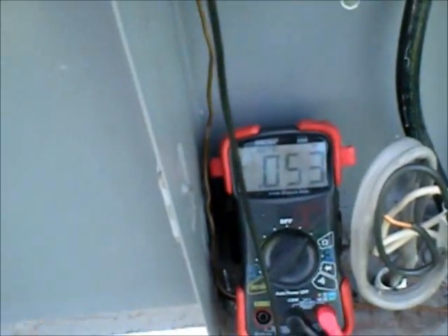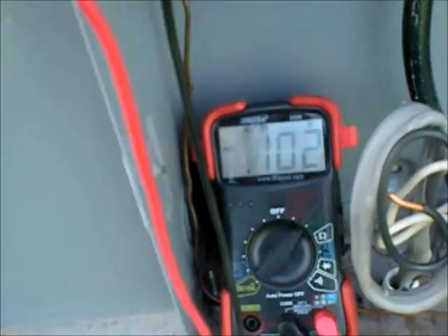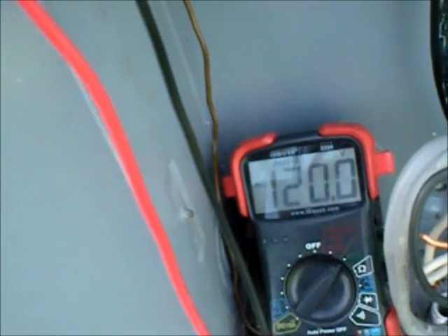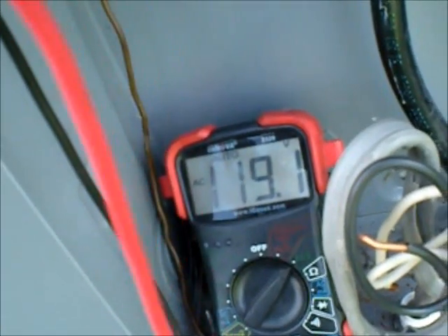This is the art of living dangerously. I've got my breaker hooked up to my second box. Now when I touch this lug, we should see 119.1 or 120 — 120.1. The other one should be 119.1. Fantastic. That means I should be able to take my meter and just pop it in.